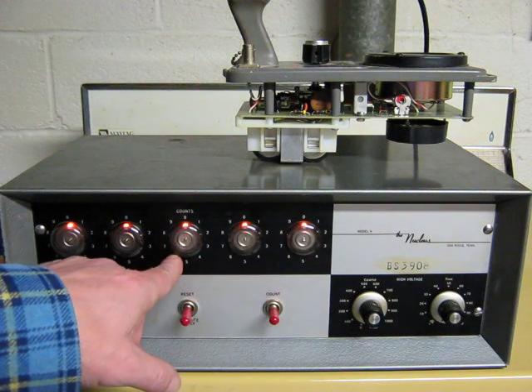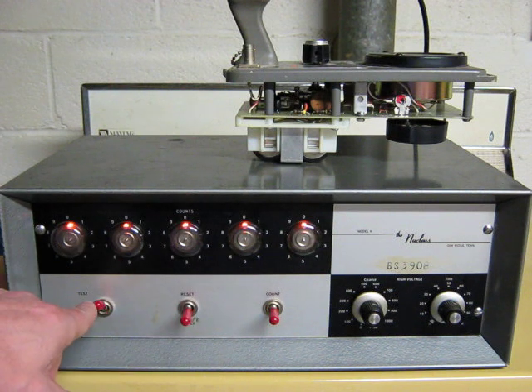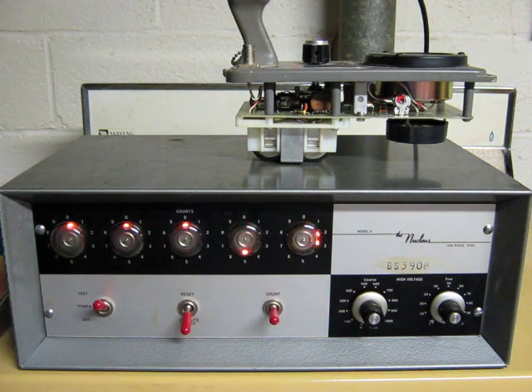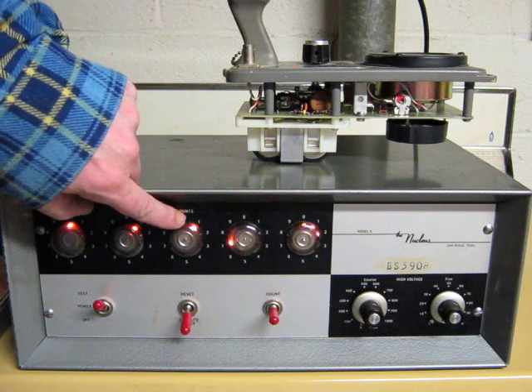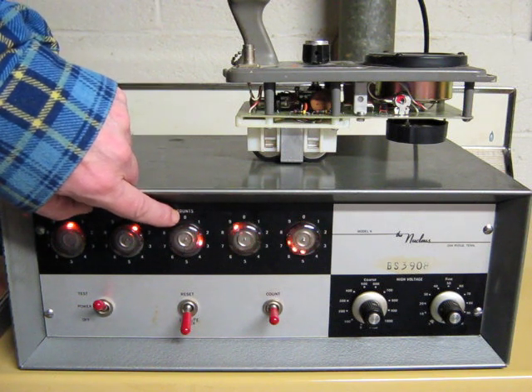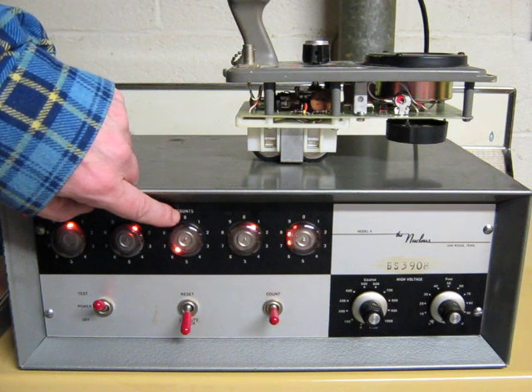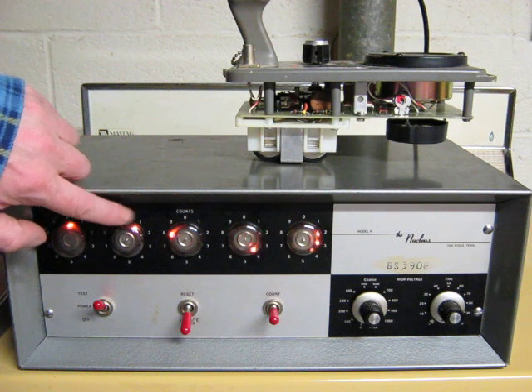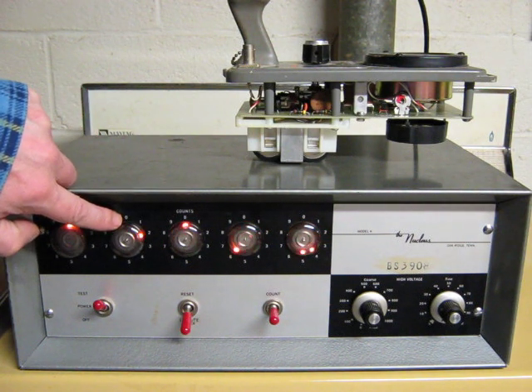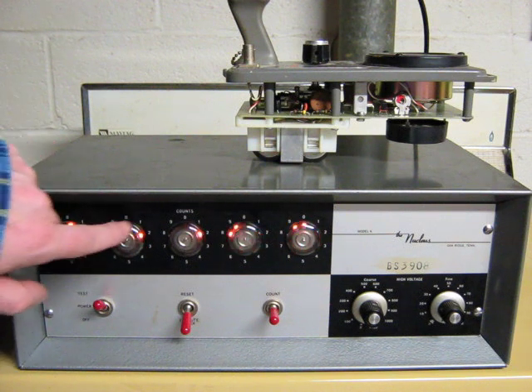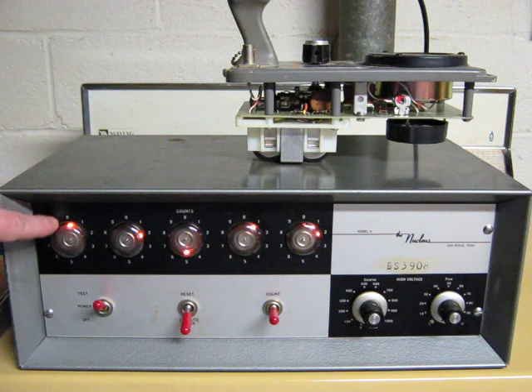Now, I can make this begin counting in test mode. 60 hertz, 60 pulses per second coming in, and so here we go. You see, every time this passes 0, this one advances. Same thing with him. Watch this, when he gets to 0, he'll move. And this will go on. If this keeps spinning, he'll advance too.